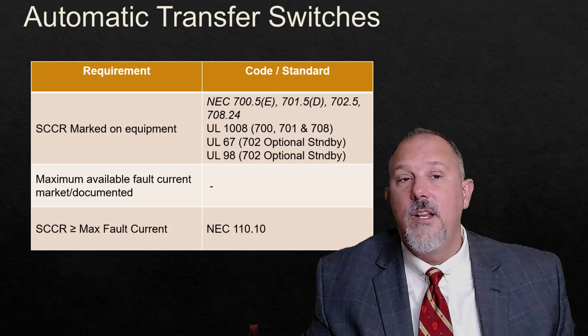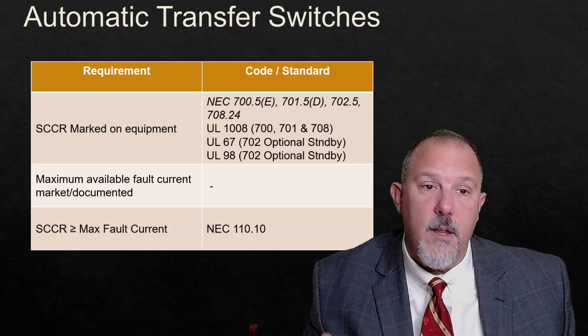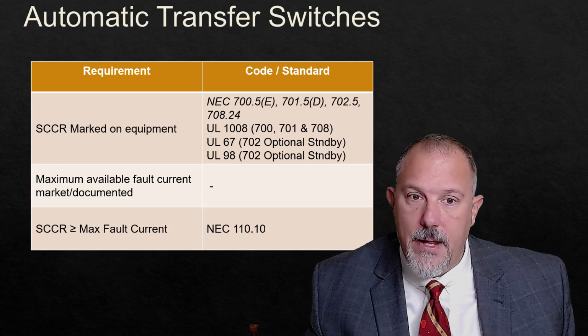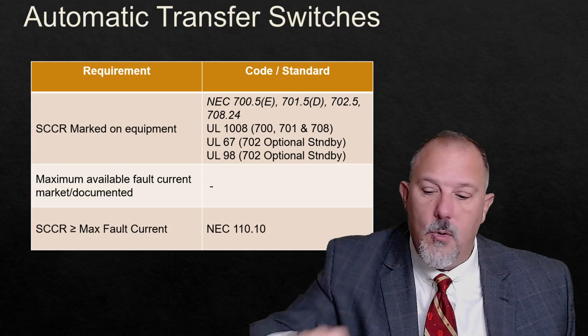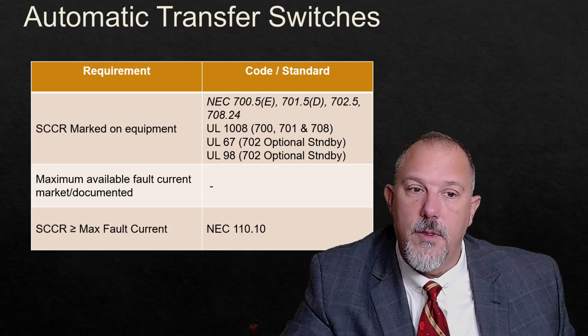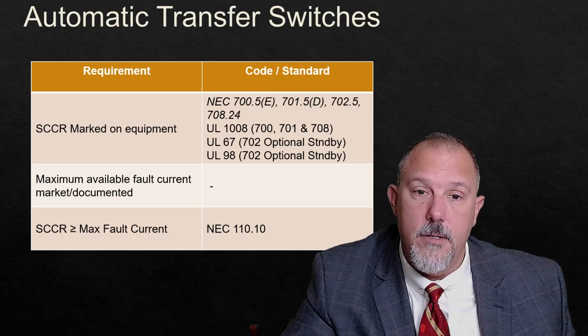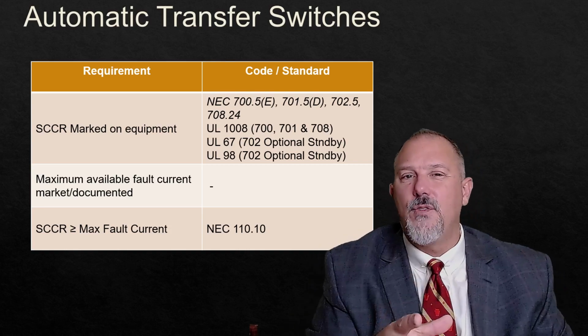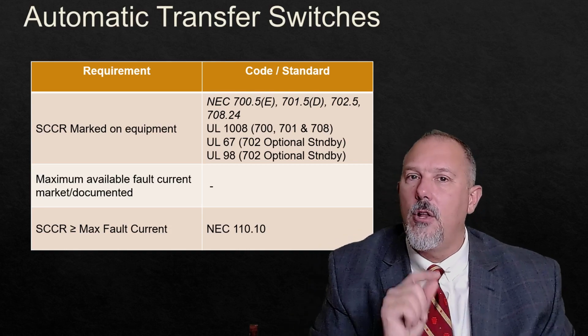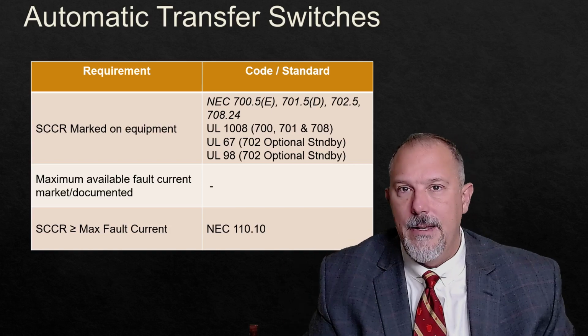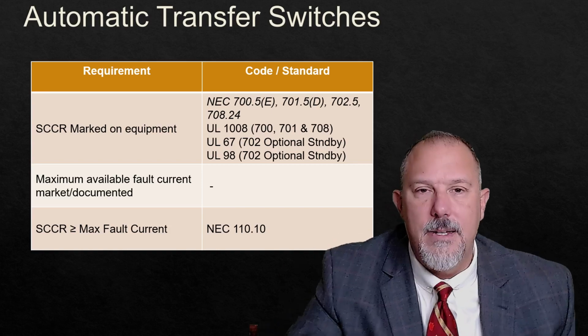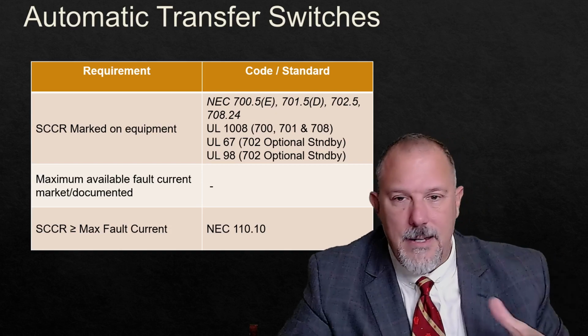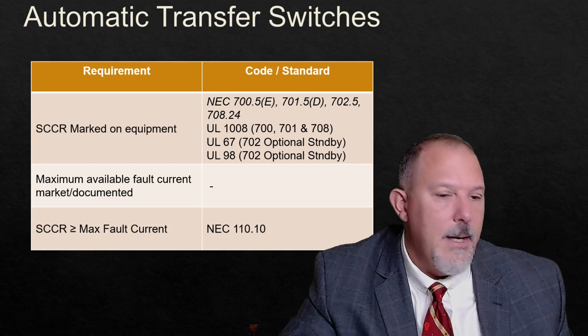There's no requirement to either document or mark the maximum available fault current on any of that equipment. And as per 110.10, you always have to make sure that the rating exceeds the available fault current. And in many cases on the automatic transfer switch, you've got to be careful because they call that a withstand and closing rating. They're the same thing, basically. I mean, not technically, but basically.